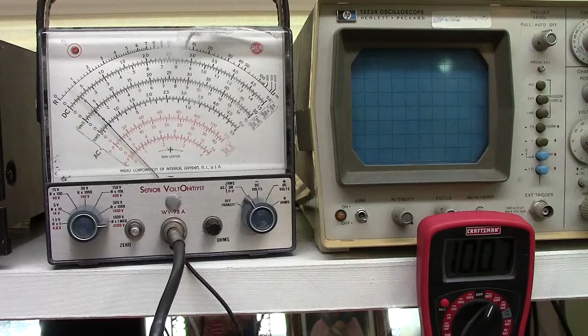So we'll click this up to the 500 scale, and it's going to run back down to 100. And click at the 1500 volt scale, and it's going to eventually get back down to 100 again. It looks pretty good. It's probably off by maybe 2%, something like that, which is perfectly acceptable for what I'm working on here in the lab.